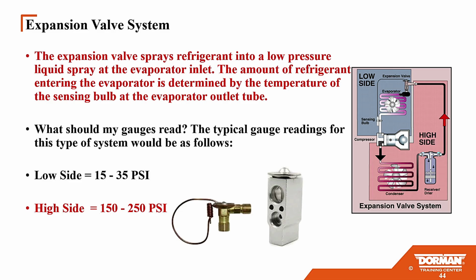The expansion valve, I briefly had a little bit on that. Expansion valve sprays refrigerant into a low pressure liquid spray at the evaporator inlet. Amount of refrigerant entering the evaporator is determined by, there's again, the temperature pressure relationship. Sensing bulb at the evaporator outlet tube. Okay, so you got different ways of getting that temperature. What should my gauge read? 15, 30, this isn't cast in stone. You need to actually get into some real good books and stuff.